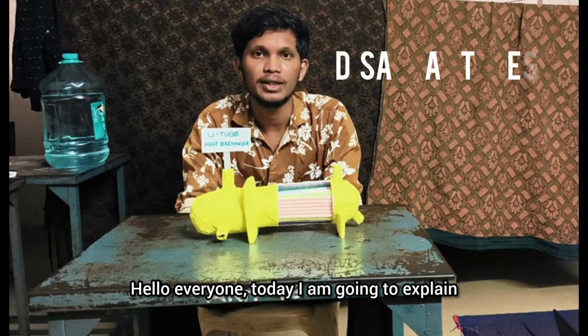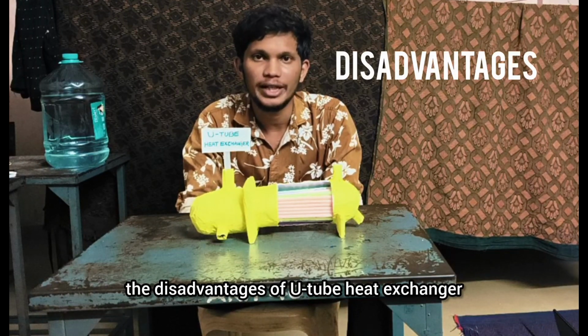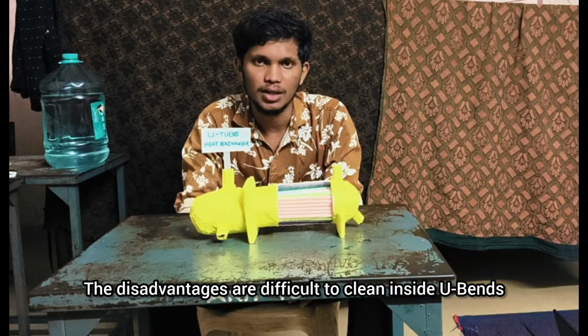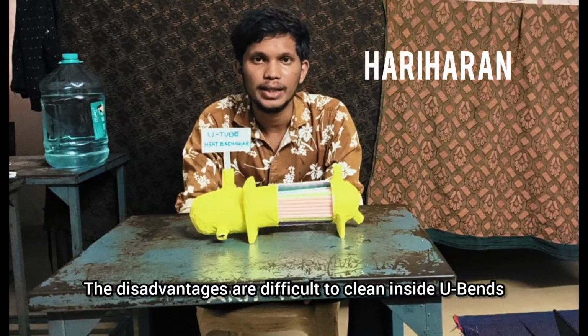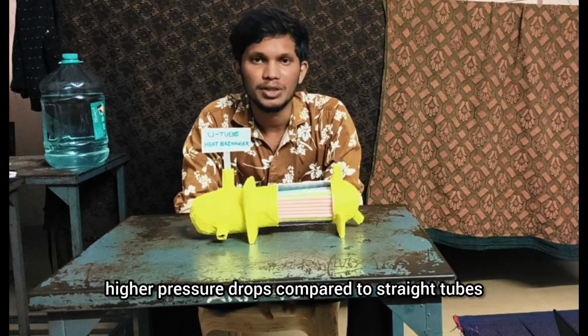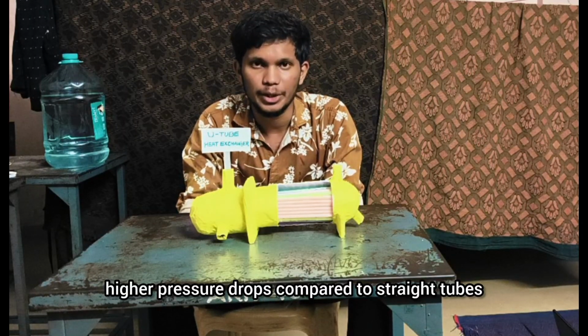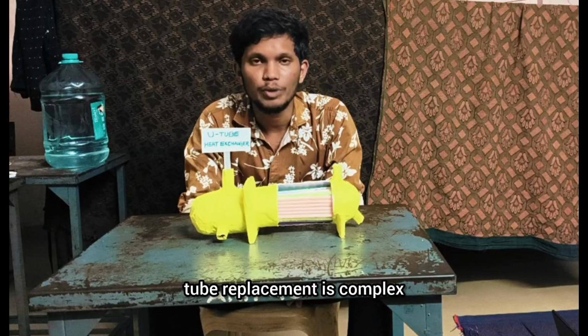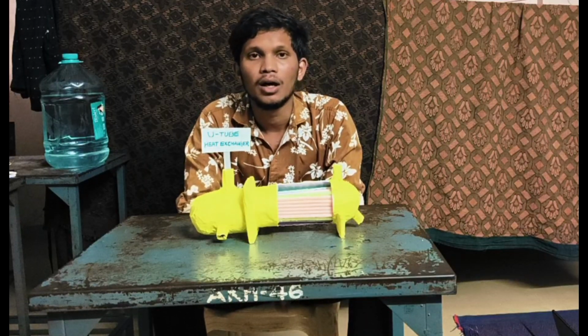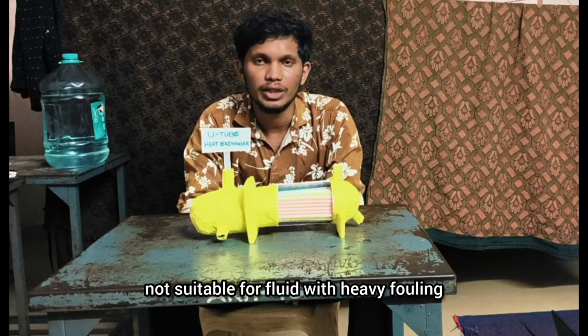Today I am going to explain the disadvantages of the U-tube heat exchanger. The disadvantages are: difficult to clean inside U-bends, higher pressure drops compared to straight tubes, tube replacement is complex, and not suitable for fluid with heavy fouling.